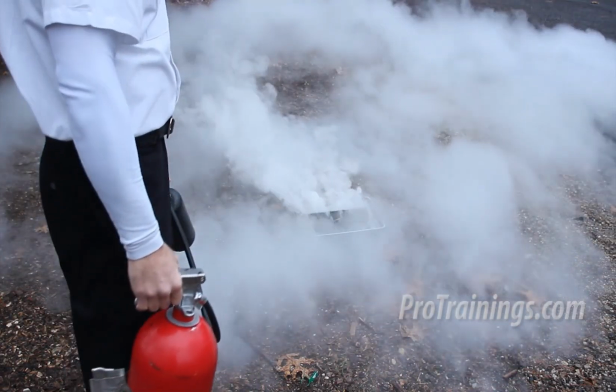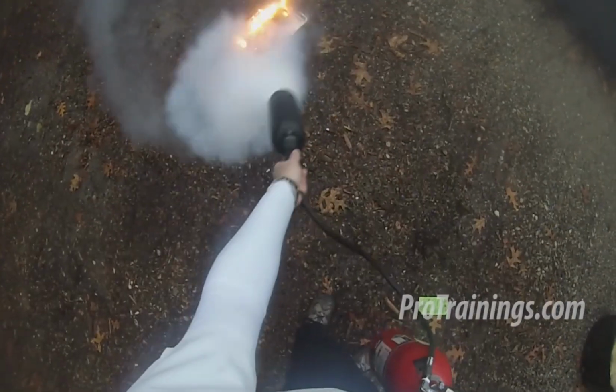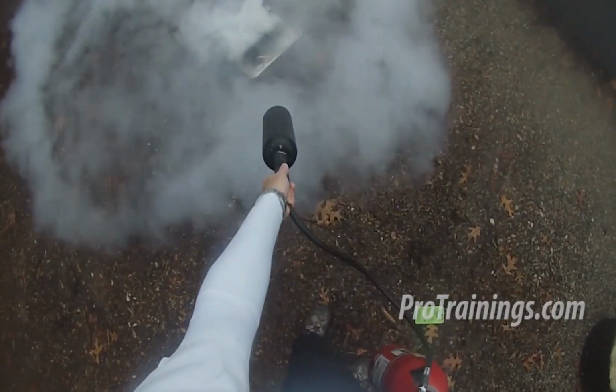Another type is a carbon dioxide or CO2 fire extinguisher. Now, these are used for Class B and Class C fires. Class B fires involve flammable or combustible liquids such as gasoline, kerosene, grease, and oil. A Class C fire, however, involves electrical equipment such as an appliance, wiring, or circuit breakers and outlets. Now, CO2 extinguishers contain just that, carbon dioxide, a non-flammable gas, and they're highly pressurized. In fact, the pressure is so great in some of these that it's not uncommon for bits of dry ice to shoot out of the nozzle when you spray it.